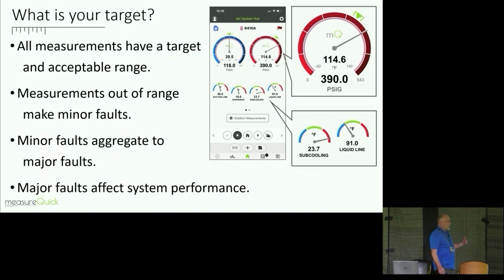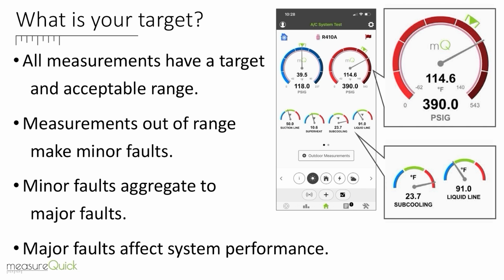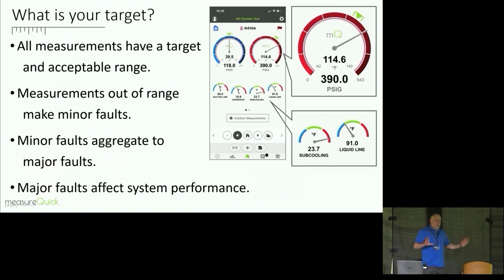The key thing we want to ask now that we've got all our probes in the right location is: what's your target? And are all your measurements in acceptable range, right? And this was a hard thing for me when I first started in the industry, because for years and years and years, I realized I was making measurements and writing them down on my work order, but I really didn't have a good understanding of what that measurement should be. In other words, I measure voltage. There's utilization voltage ranges, right? We are within the utilization range. What should our static pressure be?